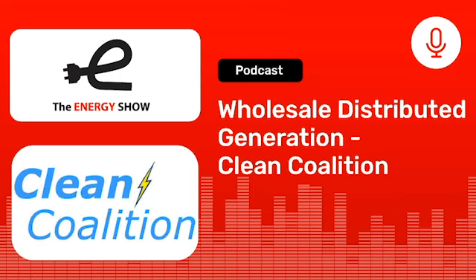But what we found here in the area around University of California, Santa Barbara - and specifically this data is from UCSB - is that if you have enough solar to net zero your site, and you put 2 hours of energy storage on it... so for example, let's say we have 100 kilowatts of solar needed to net zero the site, then we put 200 kilowatt hours of energy storage on it. That's how the 2-to-1 ratio works.